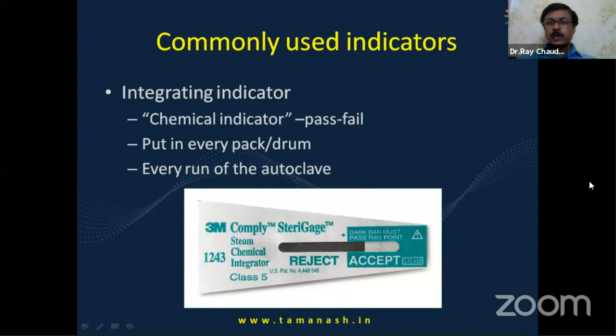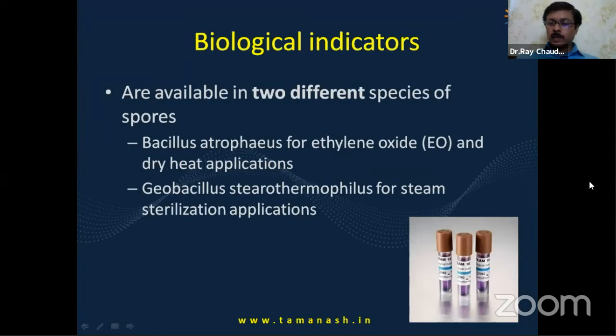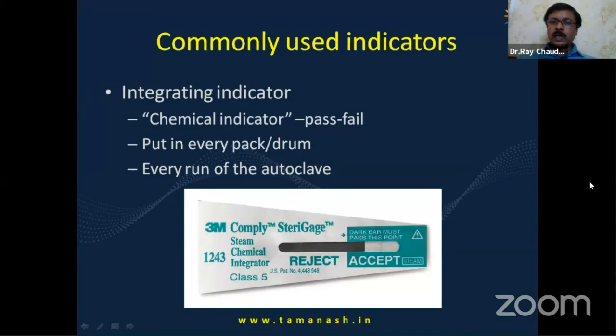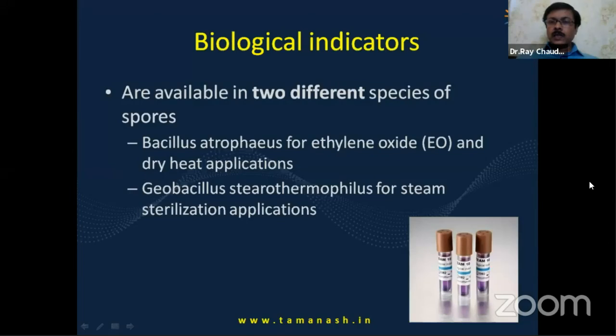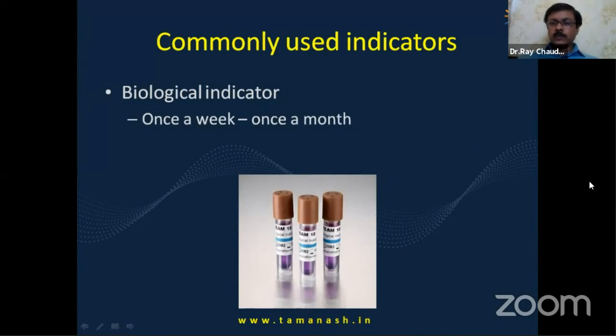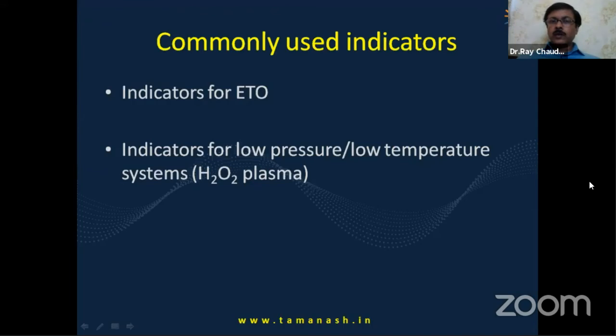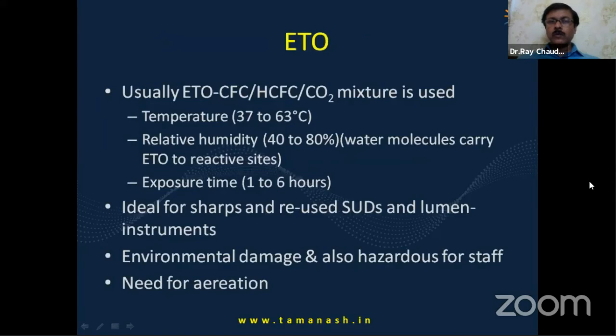The integrating indicator or the chemical indicator is a pass-fail indicator, which checks both temperature and pressure. And biological indicators, so integrating chemical indicators should be used in every run of the autoclave. Biological indicators or BI indicators contain a type of bacillus, spores which are damaged by heat and steam, and these have to be tested. Depends, either once a week or once a month, or whenever a new autoclave is installed or whenever it is repaired. So for ETO, the indicators are different, and there are different sets of indicators for the H2O2 plasma, etc., which we are not going to discuss.